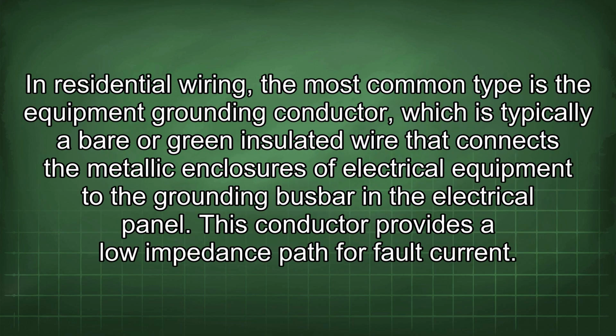In residential wiring, the most common type is the equipment grounding conductor, which is typically a bare or green insulated wire that connects the metallic enclosures of electrical equipment to the grounding busbar in the electrical panel. This conductor provides a low impedance path for fault current.